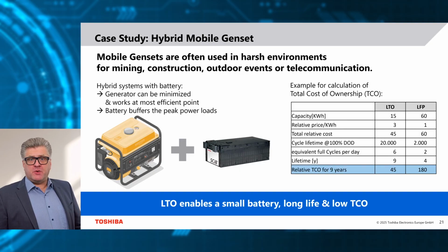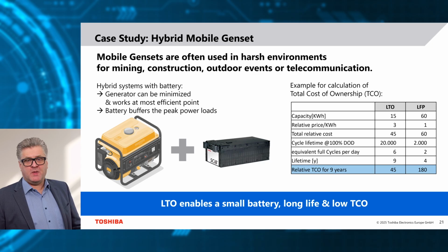Not only do they require lower capacities compared to conventional systems, we are talking about a factor of 3 or higher here, they can supply the required energy so quickly that they cover these peaks in demand and thus relieve the generator, allowing you to use smaller and more economical models and thus significantly reduce diesel consumption.